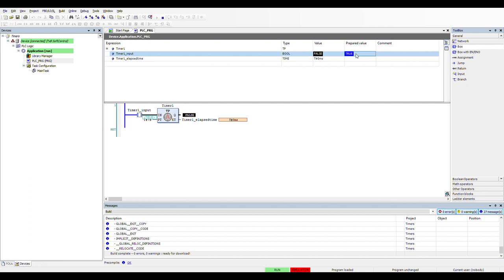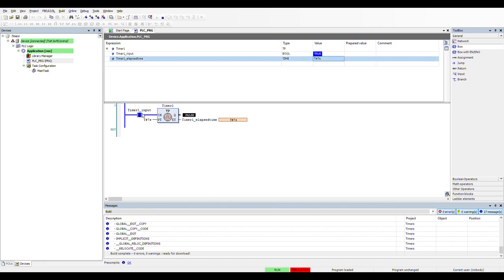One last time — I turn it on, the output is also turned on, and after 7 seconds it's turned off again, giving us a nice 7-second pulse. This can be very useful if you have a very short signal on the input side and want to prolong it, or a very long signal that you want to make shorter — you can use the pulse timer for that.